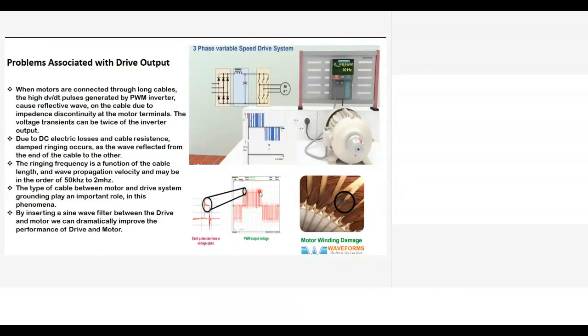Due to electrical losses and cable resistance, damped ringing occurs. This ringing is a very dangerous thing. You can see this ringing here. It causes a transient, and then the ringing also occurs. The frequency can be in the order of 50 kHz to 2 megahertz. With this type of cable between motor and drive, system grounding plays an important role in this phenomenon. It can cause common mode noise that can go back to the drive, interact with the capacitor being a low impedance path, and then cause tripping or failures also. So productivity also can suffer. Then the insulation also can suffer, as you can see, the puncturing of the insulation.